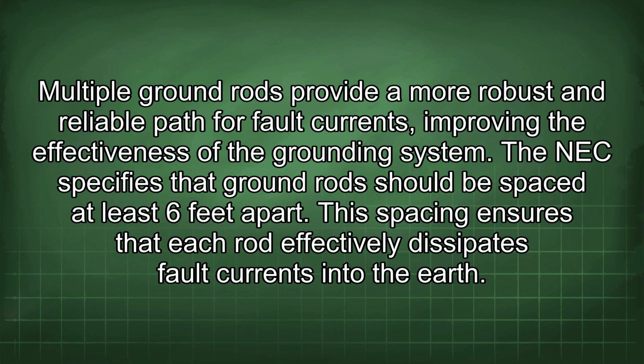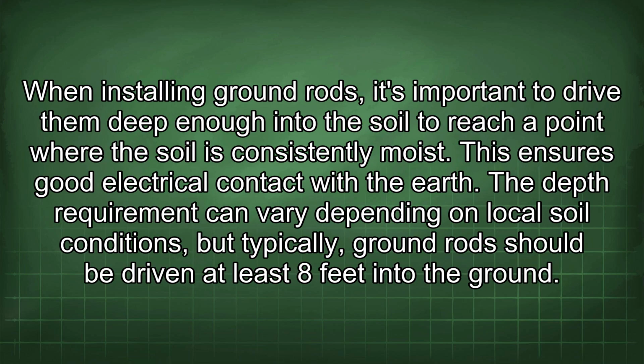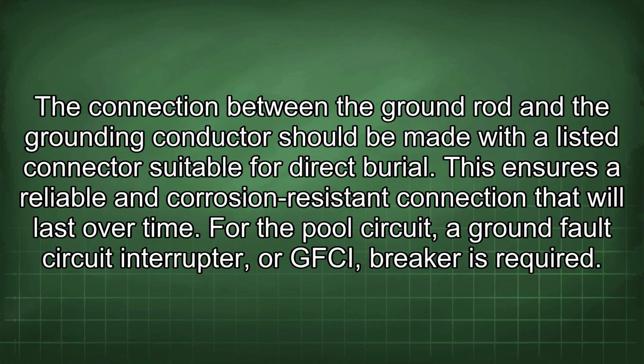The NEC specifies that ground rods should be spaced at least 6 feet apart. This spacing ensures that each rod effectively dissipates fault currents into the earth. When installing ground rods, it's important to drive them deep enough into the soil to reach a point where the soil is consistently moist. This ensures good electrical contact with the earth. The depth requirement can vary depending on local soil conditions, but typically ground rods should be driven at least 8 feet into the ground. The connection between the ground rod and the grounding conductor should be made with a listed connector suitable for direct burial. This ensures a reliable and corrosion-resistant connection that will last over time.